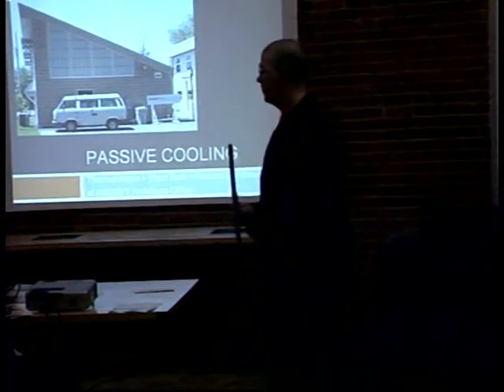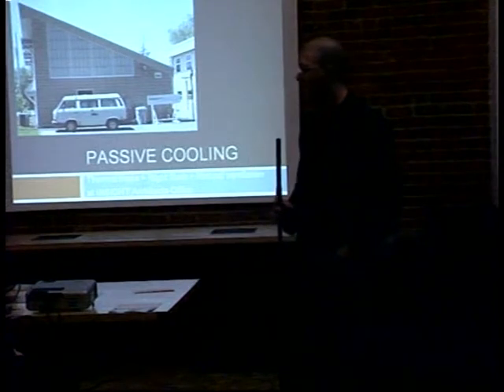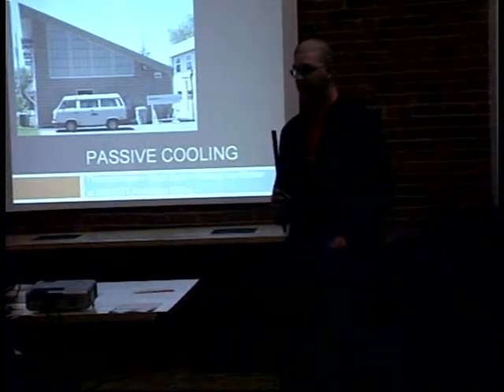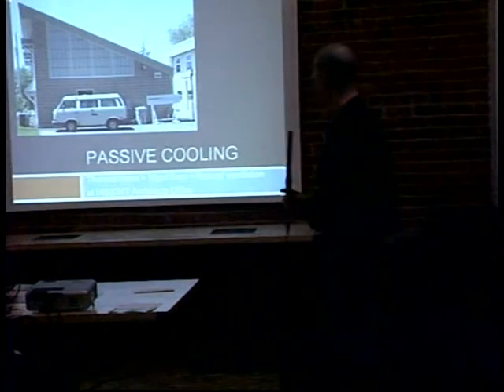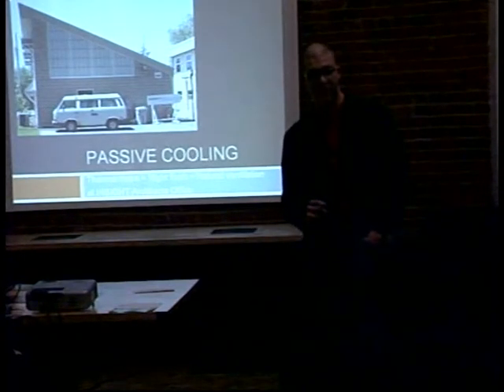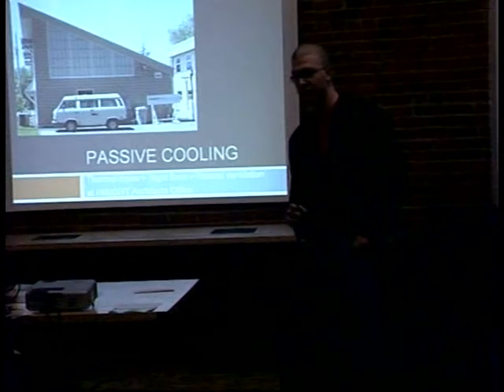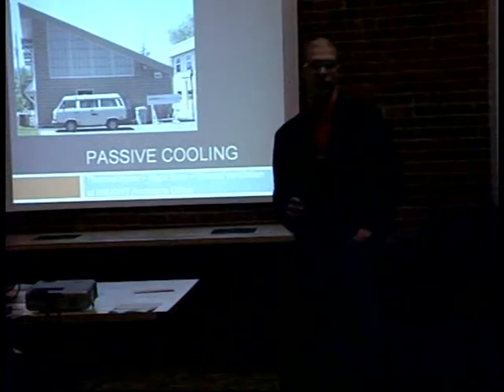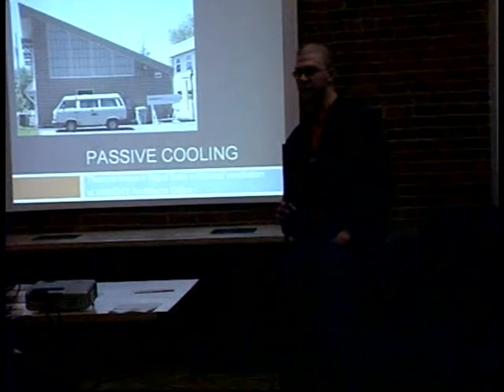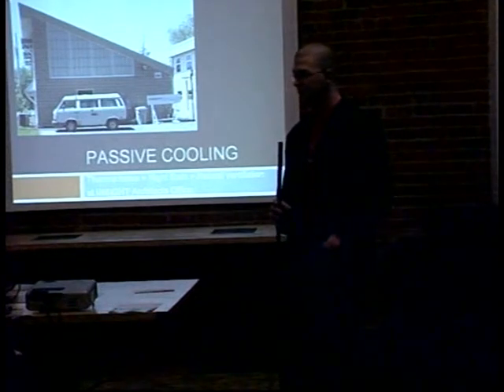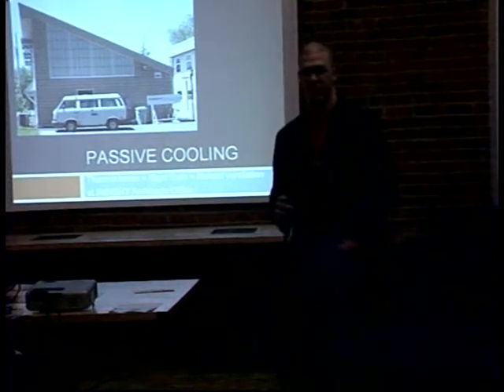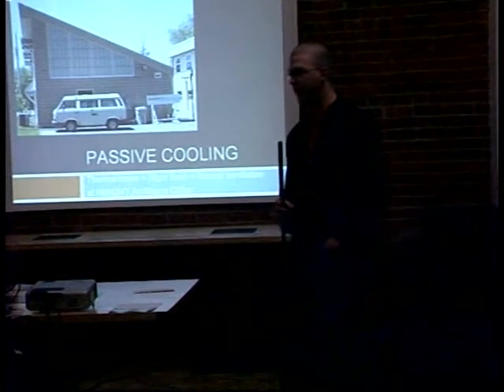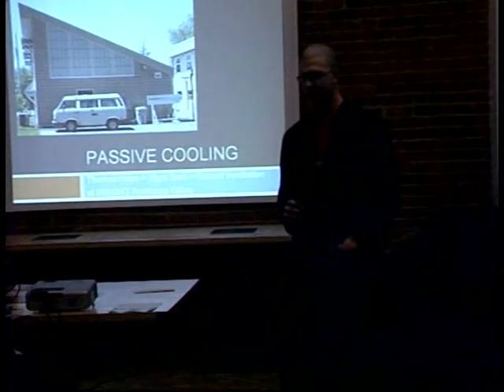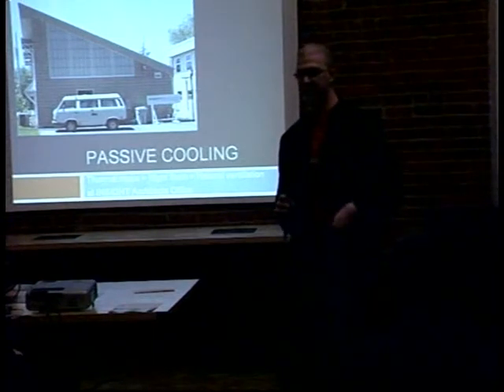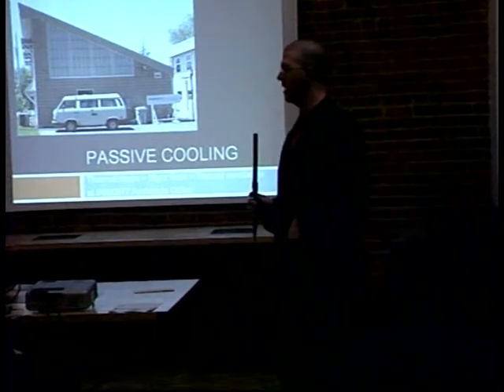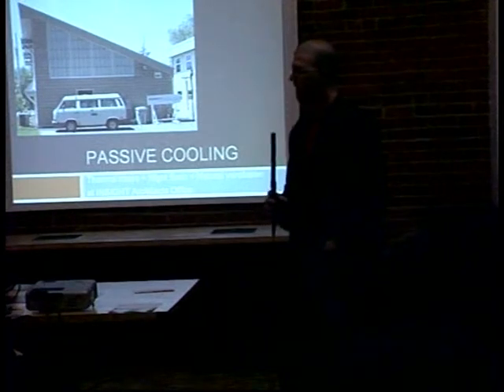I think the biggest thing we've come away with from looking at natural ventilation in Idaho over the last 3+ years is, as Ari mentioned, it's going to be a hybrid strategy - that's probably the solution. There may still be active or mechanical compressor-based cooling, but hopefully it's only 20% of the tonnage it would have been otherwise. Hopefully there's a night flush and thermal mass situation, and maybe an evaporative cooling pass in between. So I think that's where we're at with it.